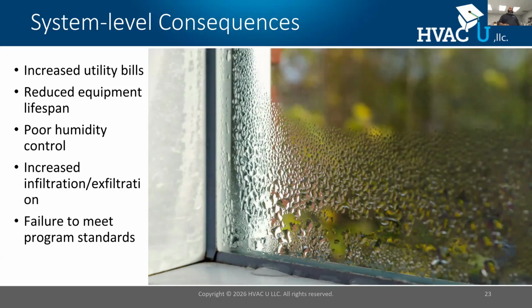It contributes to high utility bills, right? The airflow not being delivered to the space is an energy penalty because my equipment has to run longer. All right. If the equipment short cycles, that's a big problem too. A lot of people don't consider that the duct system, when it's not working properly, especially when it's due to an oversized piece of equipment, that if the equipment short cycles, equipment is rated in cycles. So if it short cycles really often, I'm going to get a mechanical failure a lot quicker than that part was designed for. I get poor humidity control. All right, I can again affect my building shell pressures, and I won't meet my program standards.